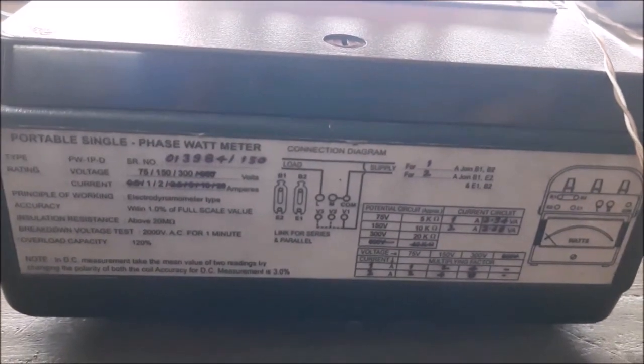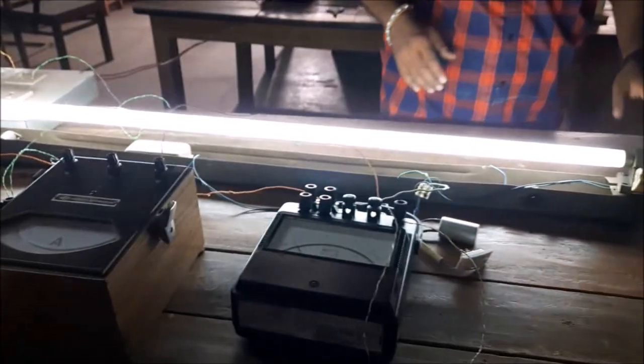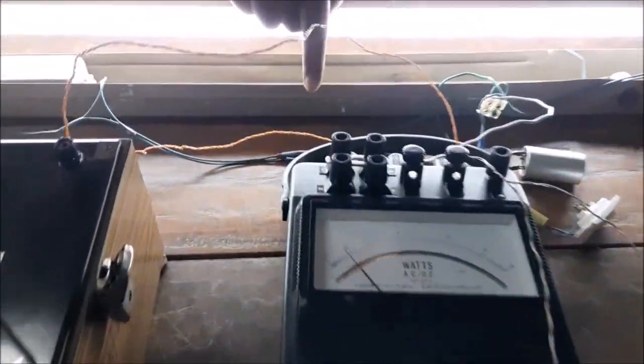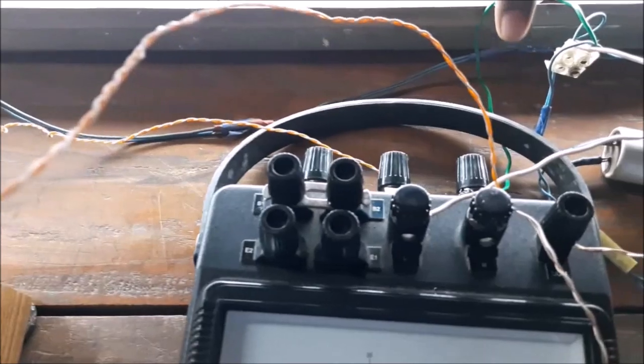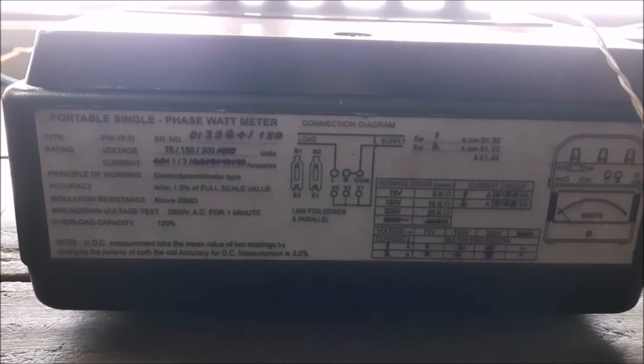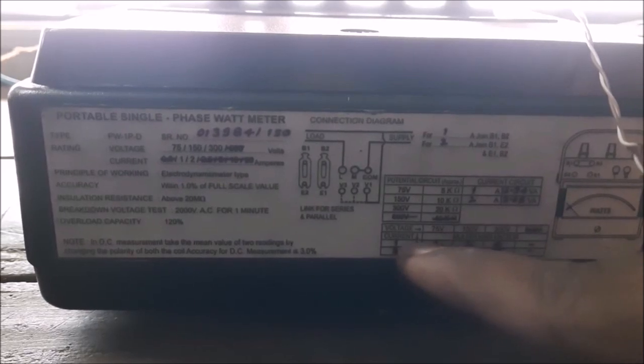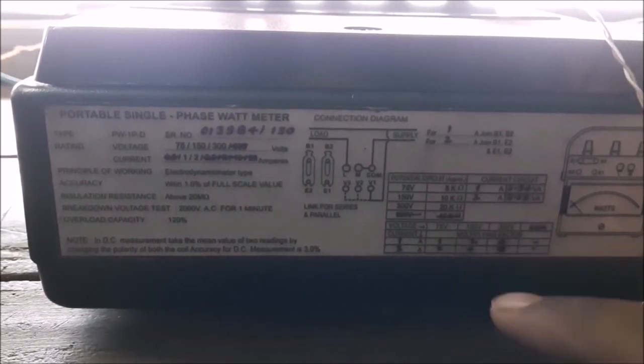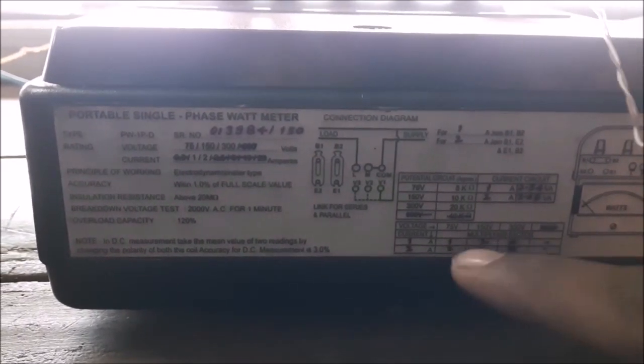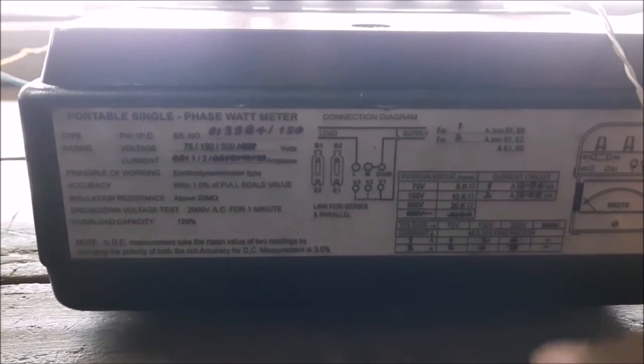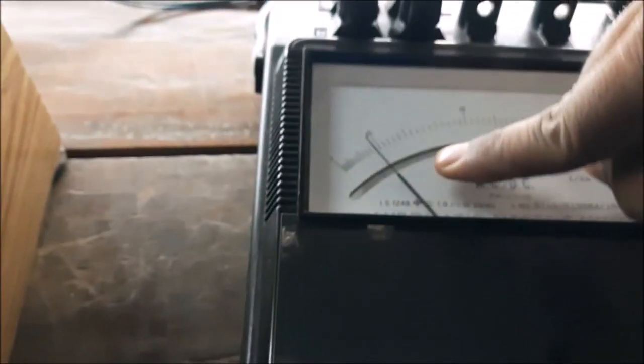Now I want to find the multiplying factor. B1 and B2 are connected and we are giving supply to the 300 volt terminal. From the nameplate reading, B1 B2 stands for 1 ampere. For 1 ampere and 300 volt, the multiplying factor works out to 4. So the wattmeter reading is the indicated value of 13 multiplied by the multiplying factor 4, giving 52 watts.